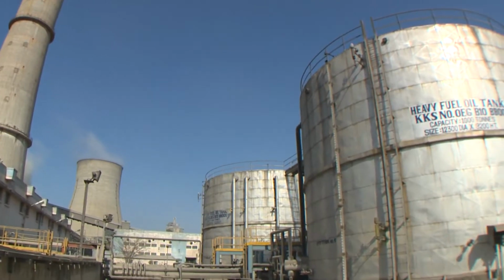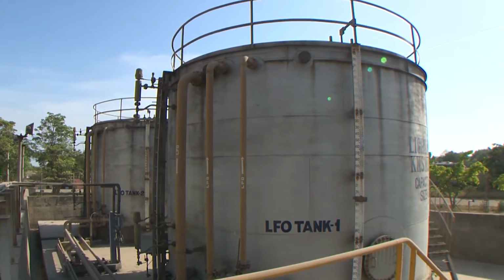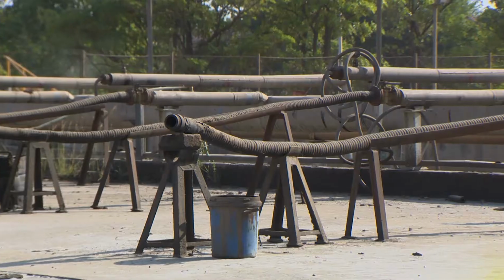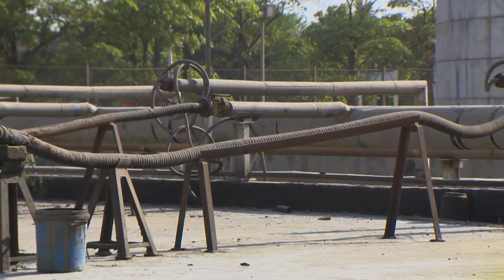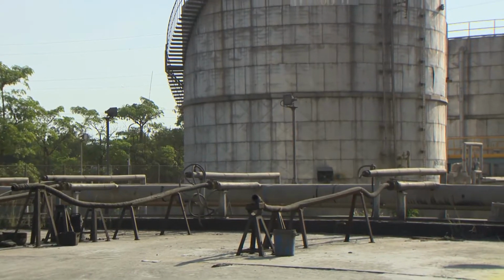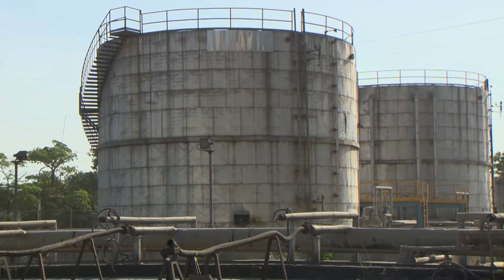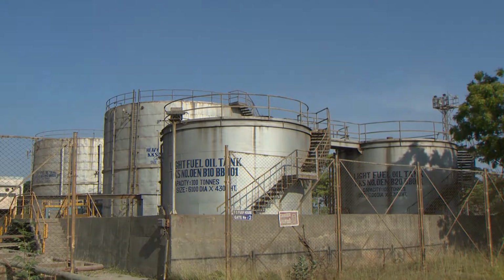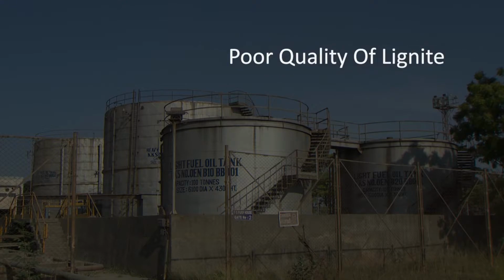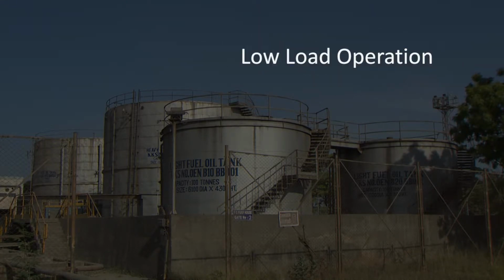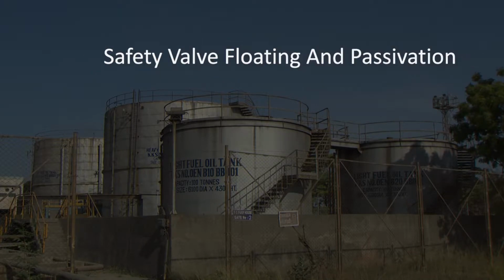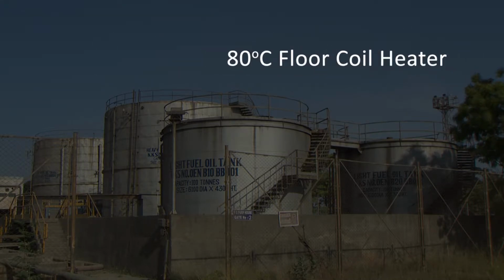Fuel oil handling system. Heavy fuel oil or light diesel oil is used as the secondary fuel for the boiler. Decanting facilities are available in power plants to transfer the oil from tankers and lorries to fuel oil storage tanks. Fuel oil is used only during initial light-up of the boiler, shutdown of the boiler, poor quality of lignite, low load operation and special operations like safety valve floating, passivation, etc. Oil temperature at the tank is maintained around 80 degrees centigrade by a floor coil heater.